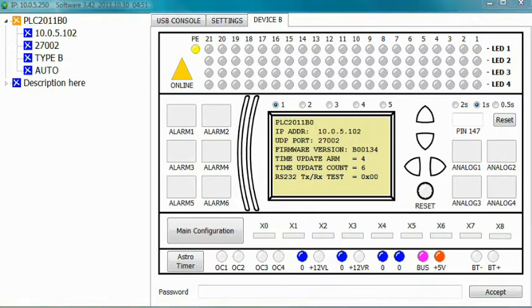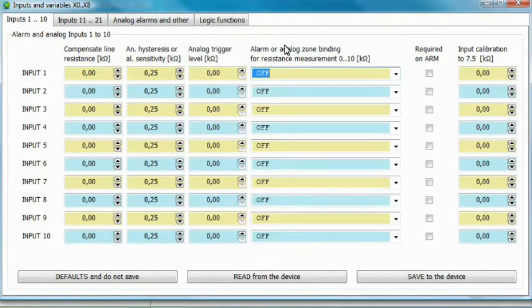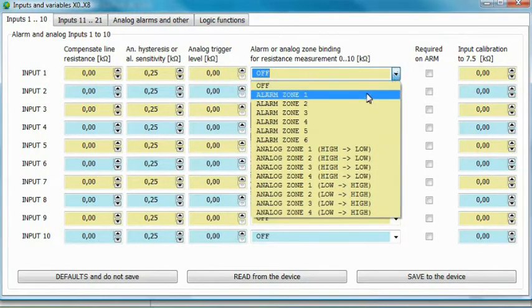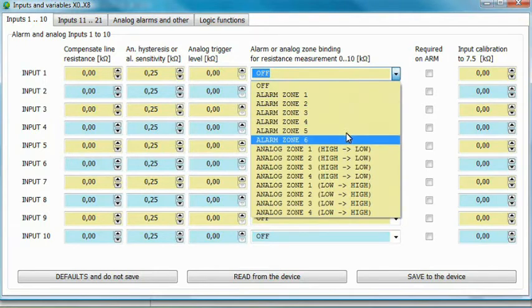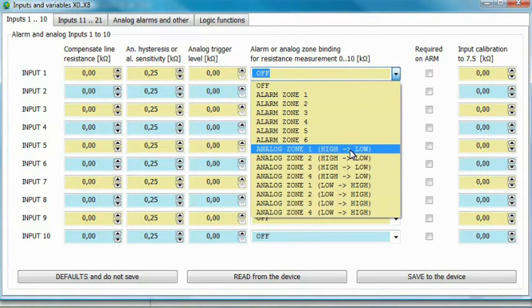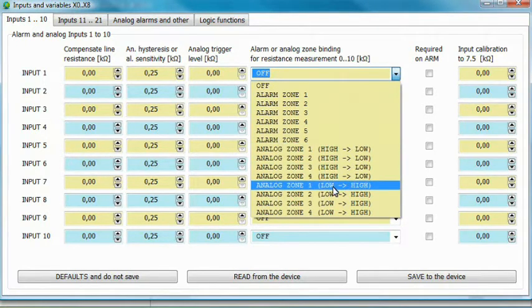Whenever the mouse cursor changes into a hand, it means that you can double-click there and a new window will pop out. In this case, this will be the input configuration window. Every input from 1 to 21 will have its own different parameters. To the input you can assign one of the following options: alarm zone, analog zone with hysteresis from high to low, and analog zone with hysteresis from low to high.